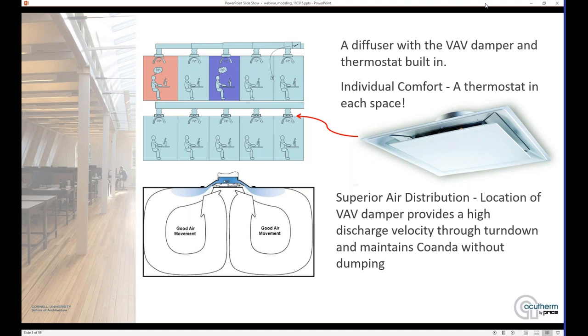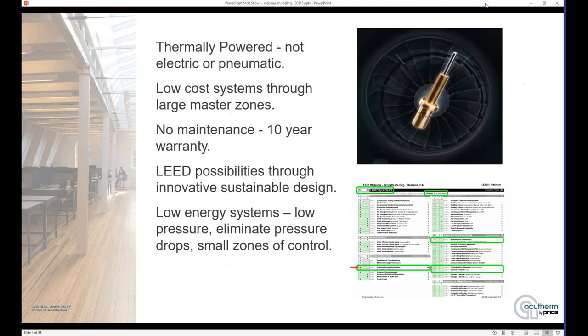We are talking about Thermafuser VAV Diffusers. They're a ceiling diffuser with a thermostat and a VAV damper built into the diffuser. By having a thermostat in each diffuser, we are able to create very small zones of control within the building and provide individual set points to each of those small zones of control. Also, by having the VAV damper located in the diffuser, it does lead to better discharge air velocities throughout the VAV operating range, which leads to better air movement and more even comfort within the space.